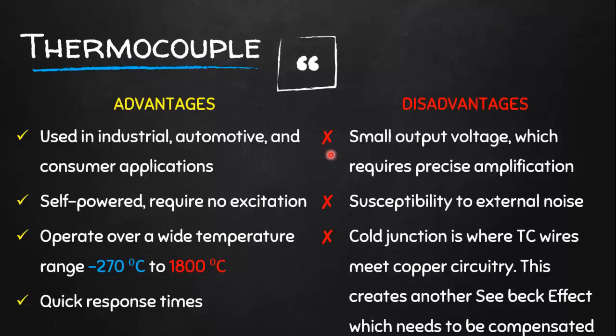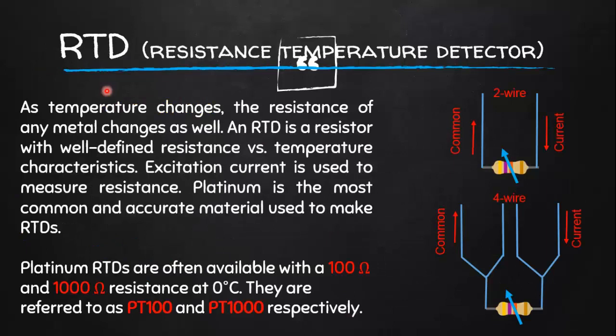The disadvantages of thermocouples include that they give a very small output voltage with respect to temperature change, which requires very precise amplification. They are susceptible to external noise because they may have long wires. There is also a cold junction where the thermocouple wires meet the copper circuitry, creating another Seebeck effect which needs to be compensated with a compensation circuit to accurately read the temperature.